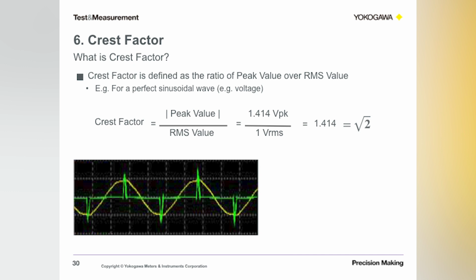Current waveforms of purely resistive loads will have a crest factor of 1.414. However, some loads, such as switching power supplies or lamp ballast, have current waveforms that are not sinusoidal, represented here in that green waveform that I have. They draw a current for a short time, and hence their crest factors could be higher than 1.414. But note that even though you have these two different types of waveforms, the RMS values of both waveforms will be the same, but the crest factors are different because the peak values are different. So when calculating power, if these peaks on voltage and currents are not detected or are clipped off, then that could affect your overall power measurements.